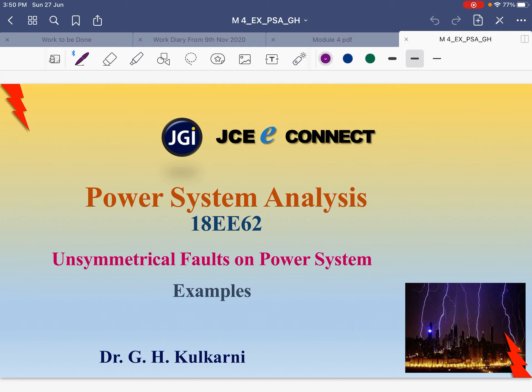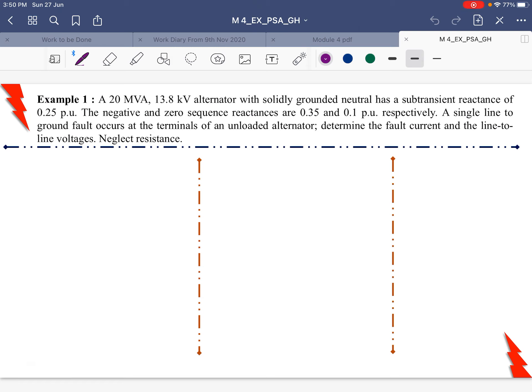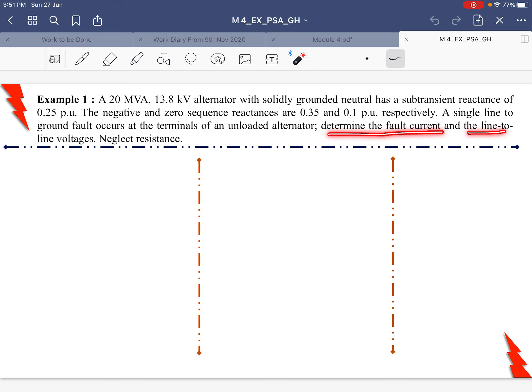We'll solve some numerical unsymmetrical faults on a power system, starting with faults on an unloaded generator. The first example: a 20 MVA, 13.8 kV alternator which is solidly grounded has a sub-transient reactance of 0.25 per unit, taken as X1. The negative and zero sequence reactances are 0.35 and 0.10 per unit respectively. For a single line-to-ground fault at the terminals of an unloaded generator, determine the fault current and line-to-line voltages, neglecting resistance.